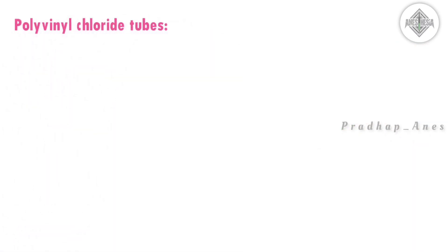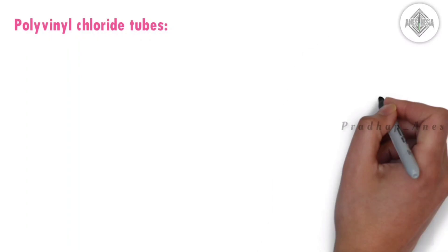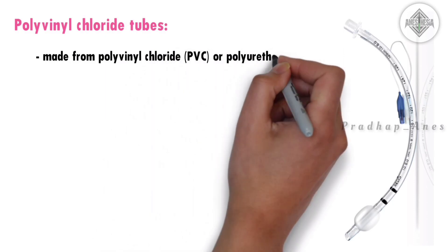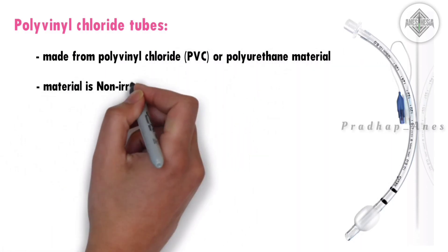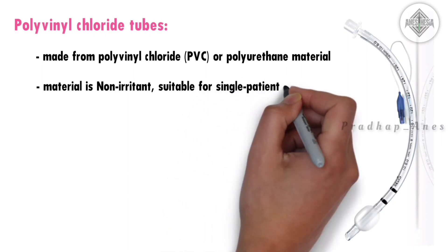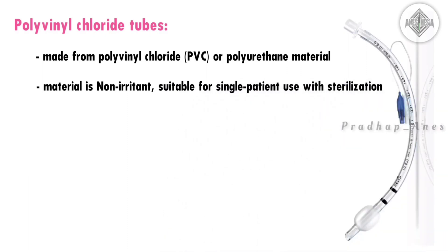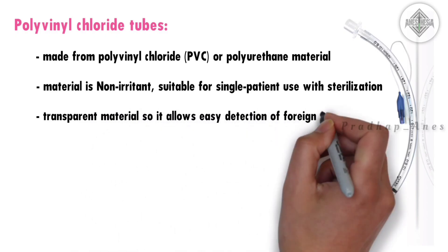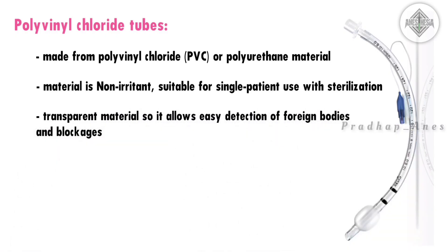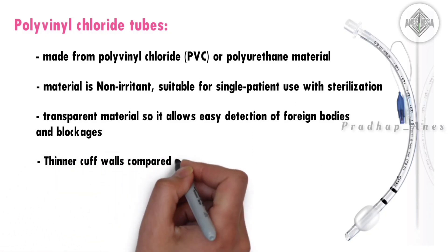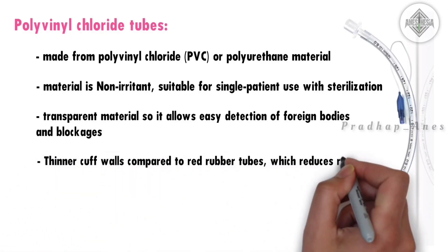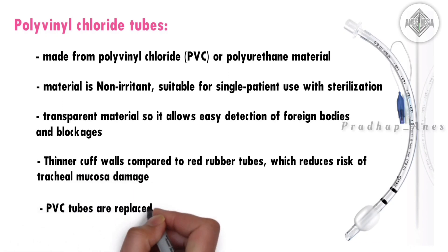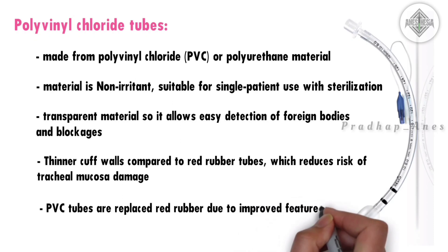PVC tubes are made from polyvinyl chloride or polyurethane material. This material is non-irritant and suitable for single patient use with sterilization. It is transparent, allowing easy detection of foreign bodies and blockages. PVC tubes have thinner cuff walls compared to red rubber tubes, which reduces the risk of tracheal mucosa damage. PVC tubes have replaced red rubber due to their improved features.